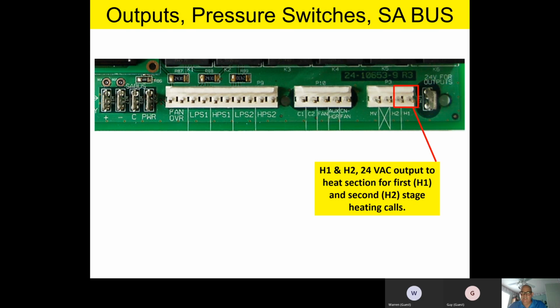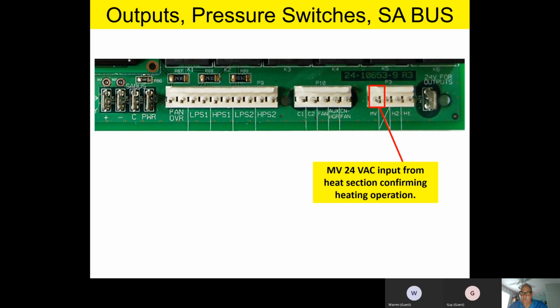Right next to it, we have H1 and H2, and this is a 24-volt output to the heating section on a unit that has a heat section, for first and second stage heating calls. Right next to that is an MV 24-volt input from the heating section to confirm heating operation. Basically, this MV tells the Simplicity control board, hey, we're working normally. Think about a gas pack for a second. I call for heat, it goes through its normal sequence of operation, and once it confirms flame, with flame proving and all the things a gas pack would have, it outputs from the heating section to tell the motherboard, so to speak, hey, we're working okay. That MV is an input from the heating section to confirm heating operation.